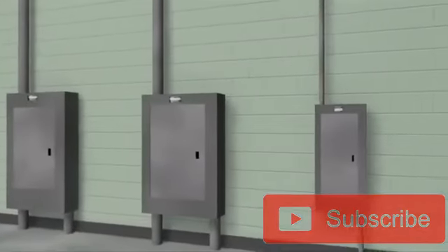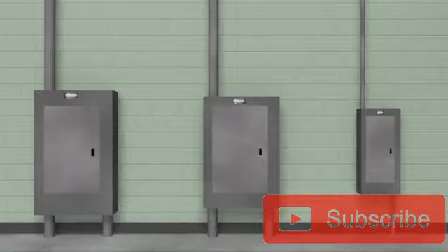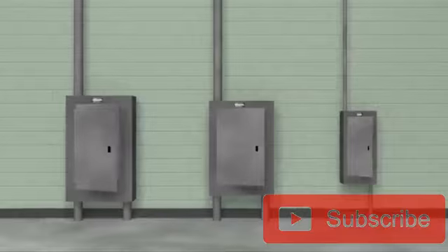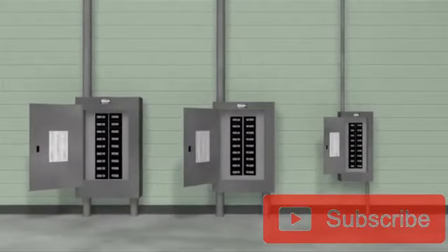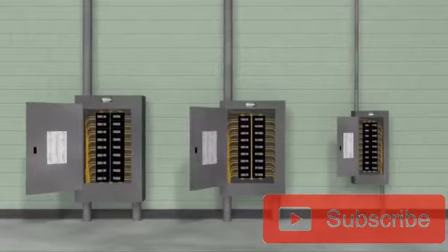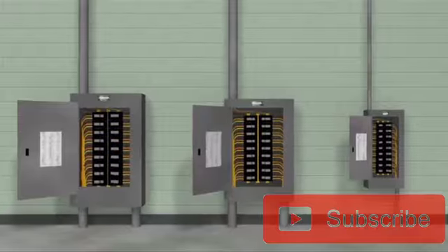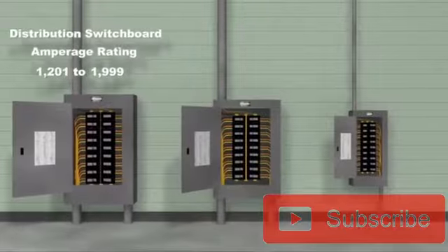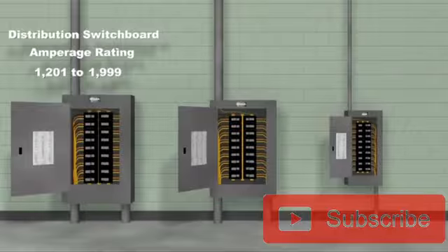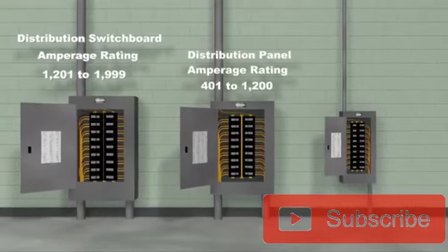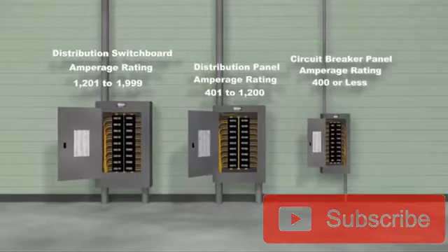A distribution switchboard, a distribution panel, and a branch circuit breaker panel all have the same functionality. They can contain many circuit breakers distributing voltage to all areas of the facility. What differentiates them from each other is their amperage rating. A distribution switchboard is an electrical panel with an amp rating between 1,201 and 1,999. A distribution panel has an amperage rating of 401 to 1,200. A branch circuit breaker panel has an amperage rating that is equal to or less than 400 amps.